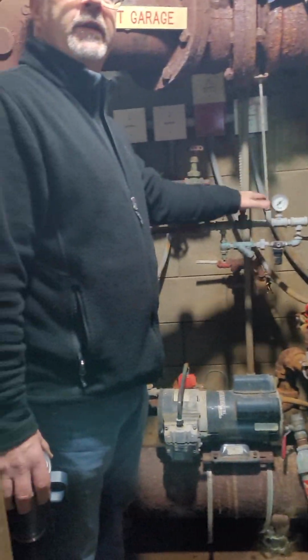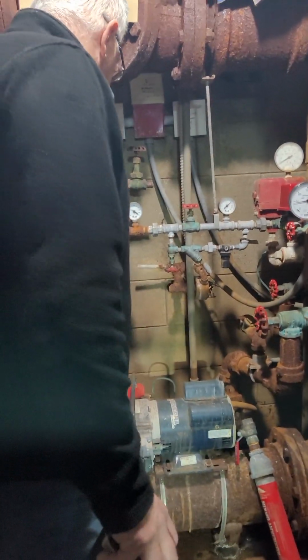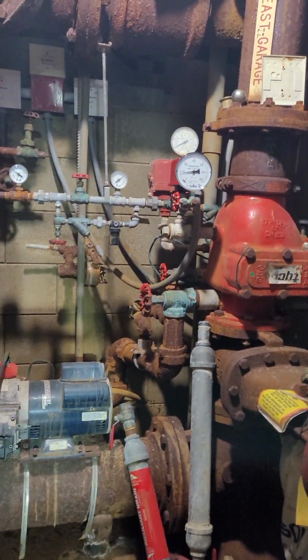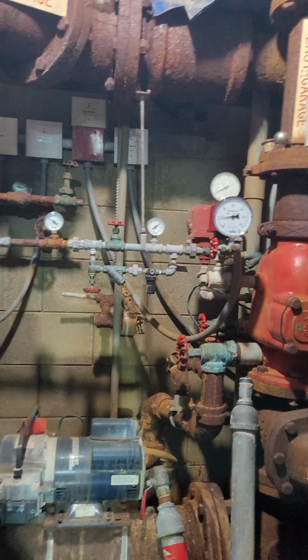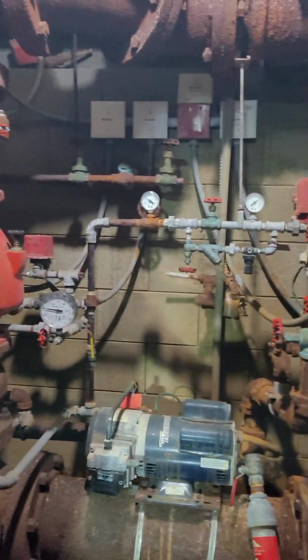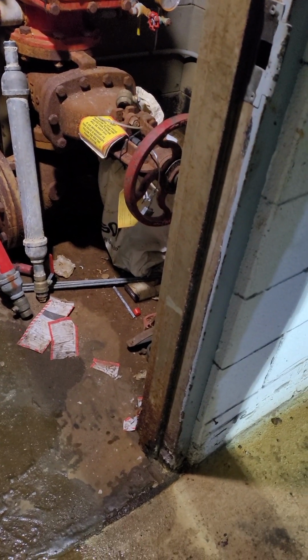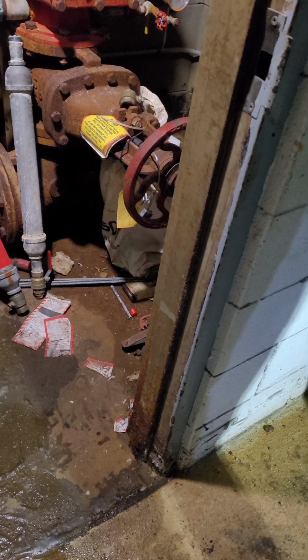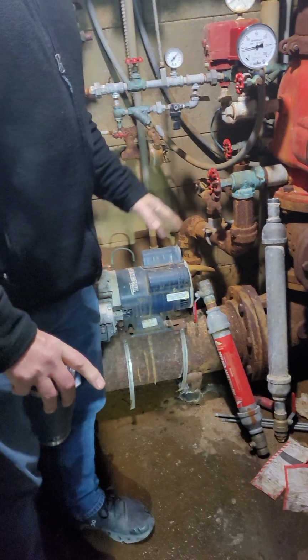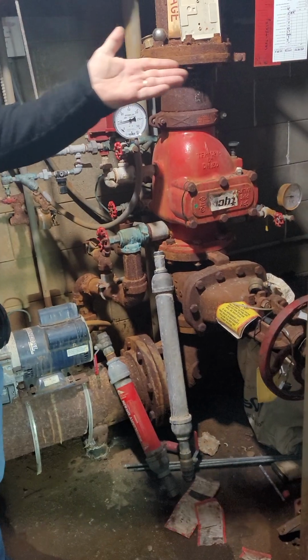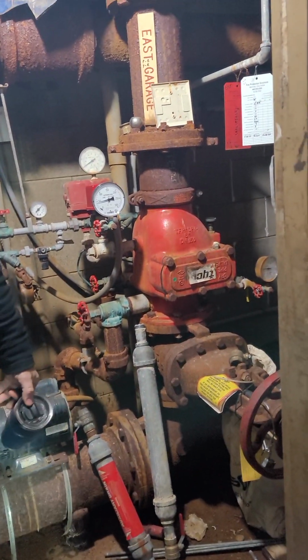Switches - oh okay, switch on. The other way to do it is to close these valves. Coming right off of your compressor, it goes up here - you've got this valve, then this valve, and this valve. You can also make sure those are closed if you want to. If you close those valves, your compressor will instantaneously pressurize because the air is only going to here, so it'll turn off and not run. But the easy way to do it is to turn the switch off.